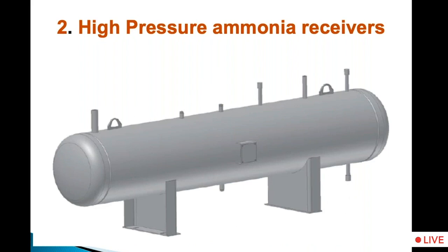The next vessel we come to is the high pressure ammonia receiver. The purpose of the high pressure ammonia receiver is to store the entire charge of the refrigeration system. If you want to do any repairs anywhere inside the system, you pump down the entire quantity of ammonia gas and take it into the receiver. So this vessel is also very, very important, and it is high pressure ammonia. It is at the same pressure as the condenser pressure, or 21 kg, or the working pressure is normally 13, 14, 15, maximum 15 kg per centimeter square gauge under Indian conditions.